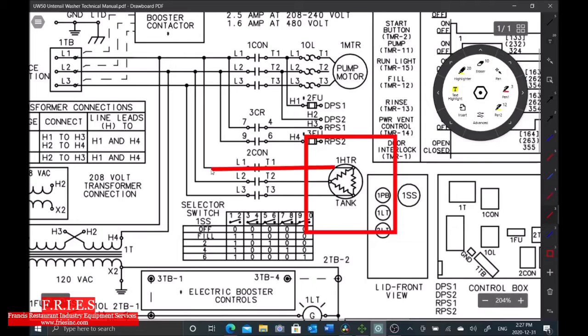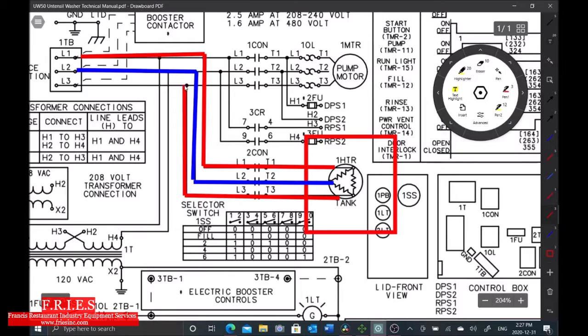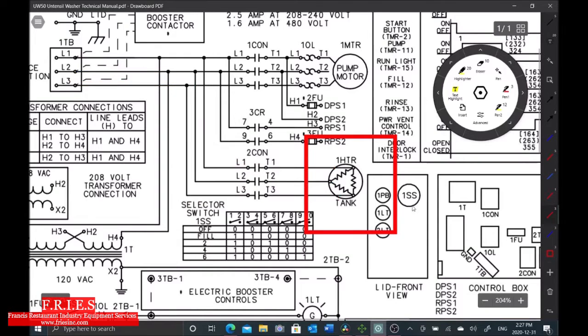So we're going to start with our T1, L1. It goes through the contactor contact, and it is a straight shot to our terminal block. L2, same thing. We come here, we go through our contactor contacts, and we're going to come right up to L2 on our terminal block, and then finally L3 is right here coming through the contacts, and that's going directly to our terminal block. Alright, so as we can see there, these contacts are not closing. Okay, we had that visual cue.